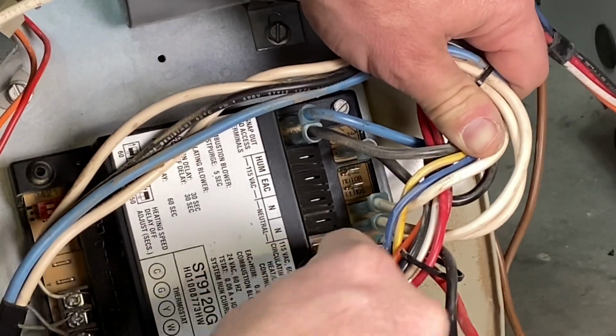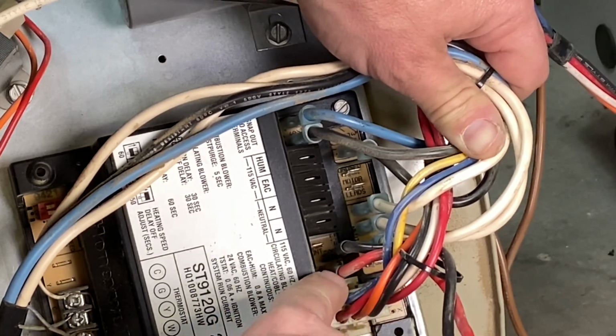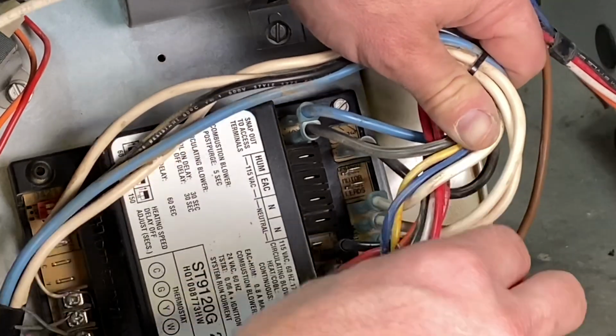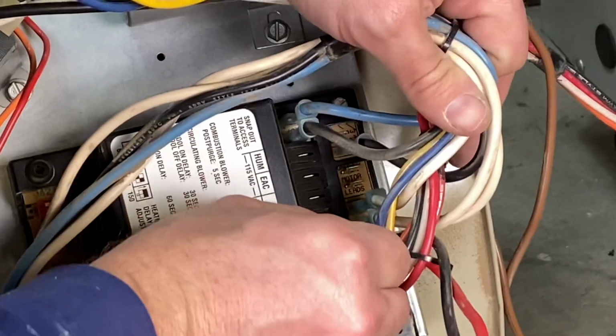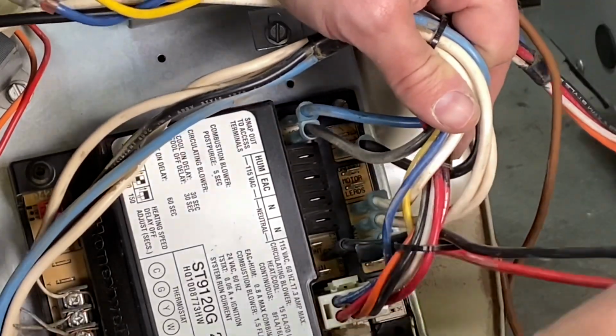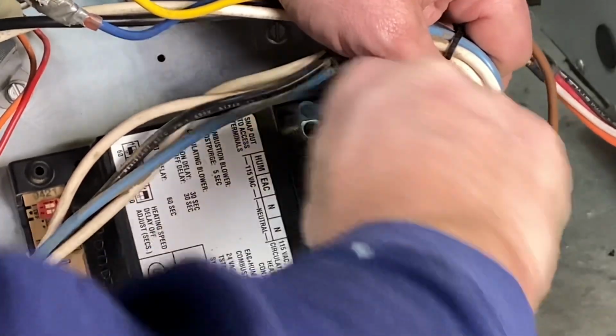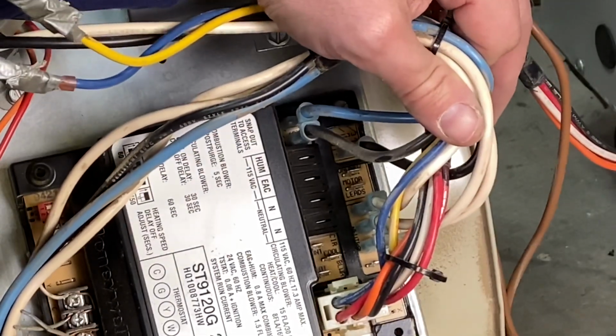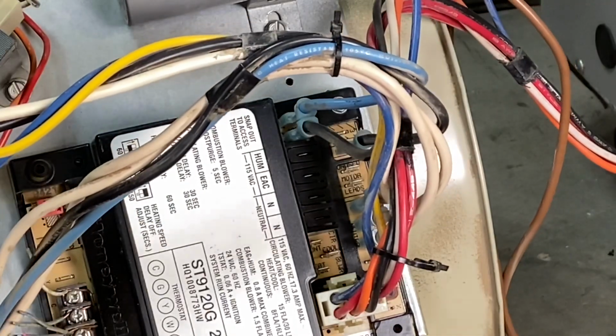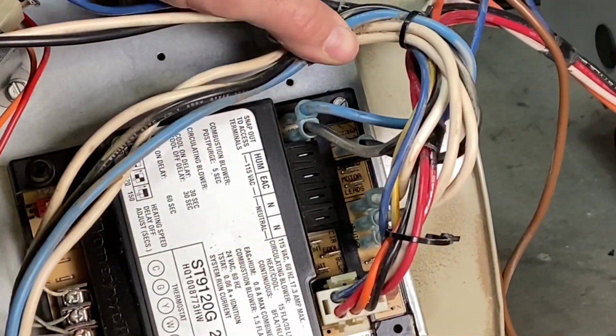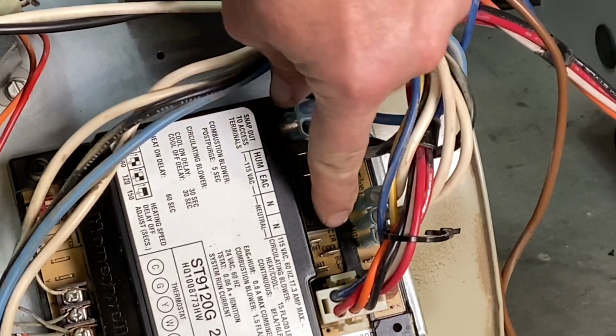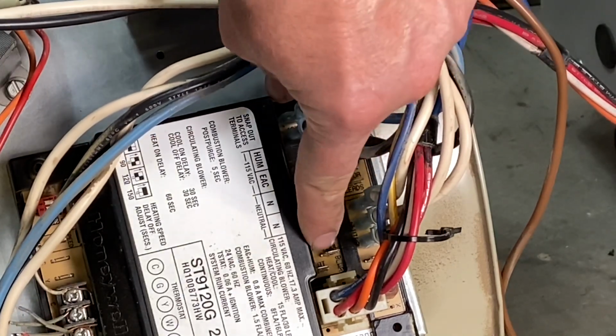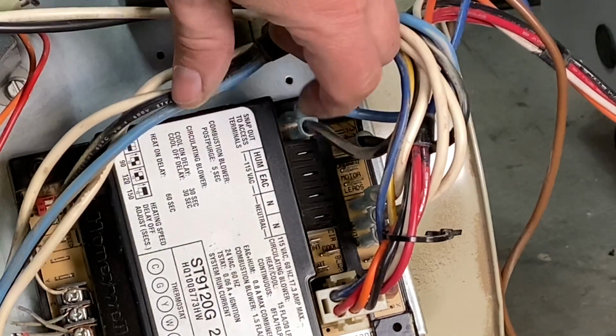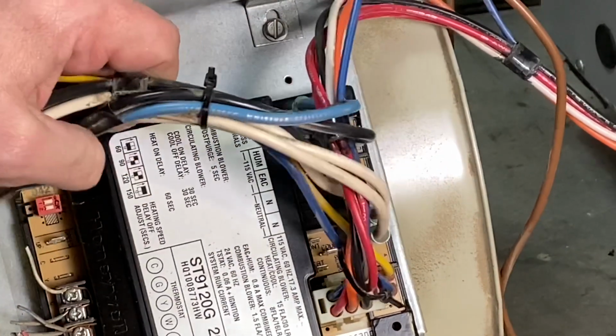The black wire is going to where it says cool, and the red wire is going to heat. So the red wire is the speed that's energized when we have a call for heating, and the black wire is when we have a call for cooling or fan only. So once they unplug those wires, our fan motor is completely separate. Let's see if we can see the cool terminal and also the heating terminal right there. So that's all it is for the fan motor.